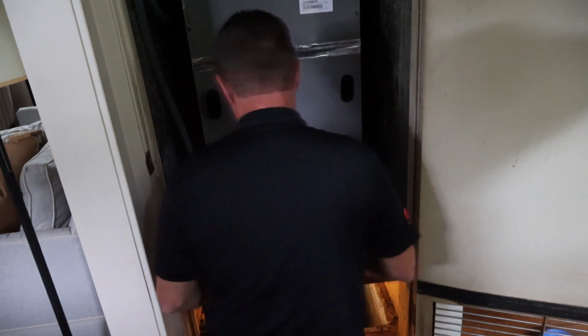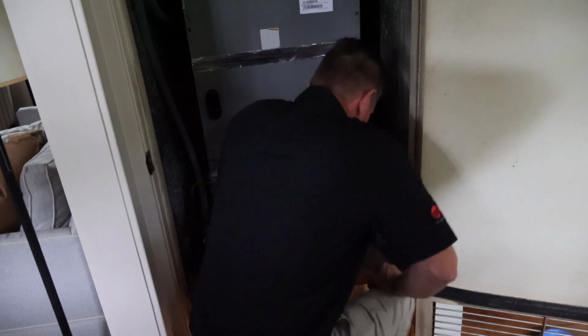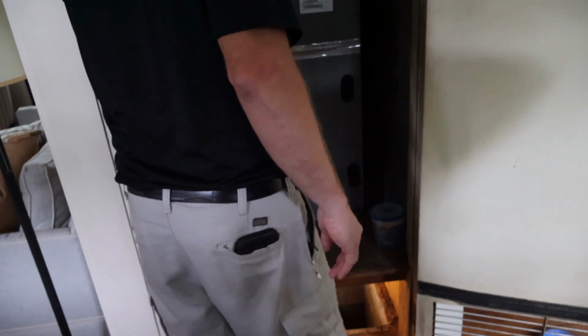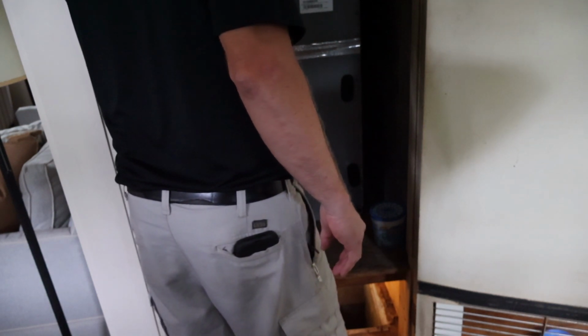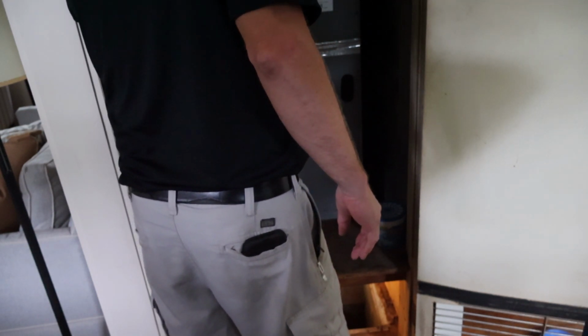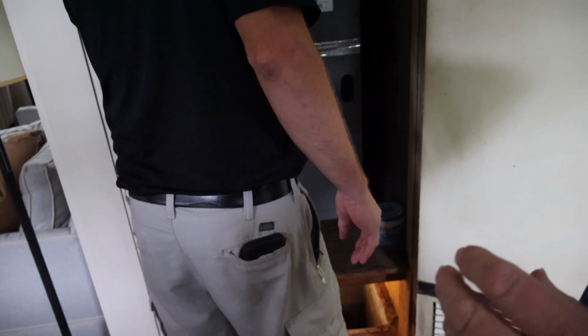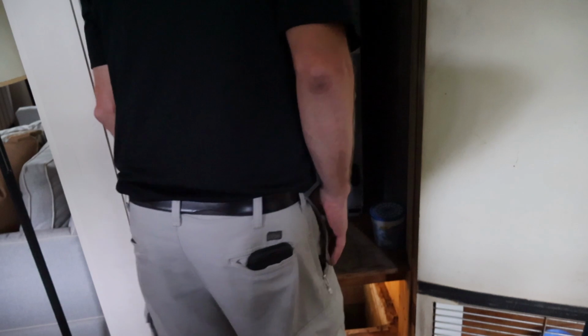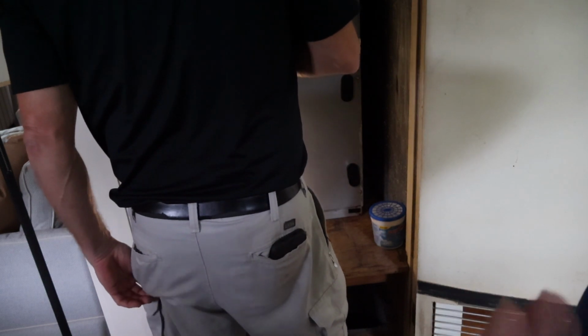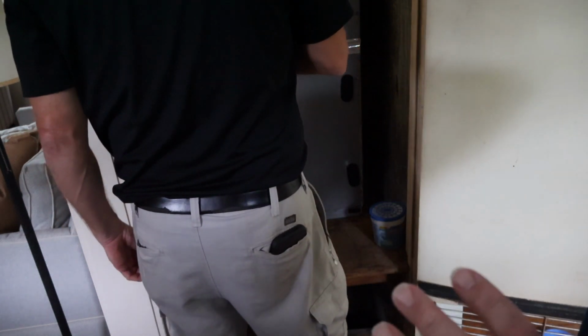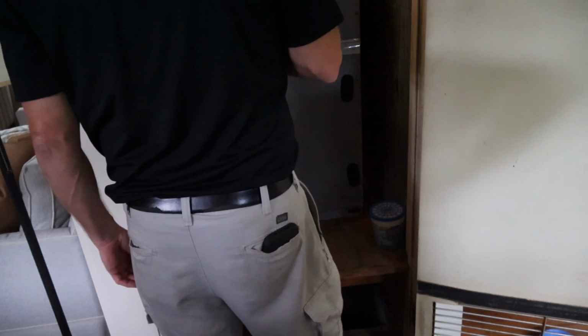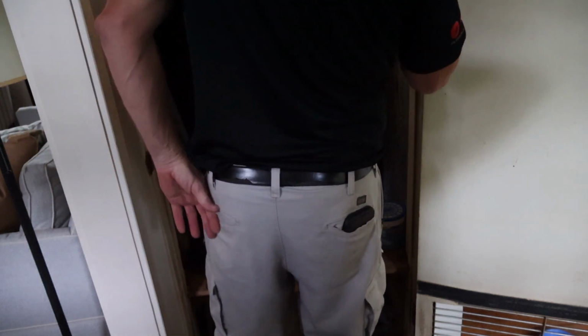And we'll come back in after we service the outdoor unit. One reason we do that is if the system is low on refrigerant, we'll have to leak check. So instead of servicing the air handling unit and taping it back up, sealing the air handler doors, we'll go outside, confirm the Freon's okay, and if it's not and we've got a leak somewhere, we'll have to take the panels back off to do a leak check. So that's why we like to do the condensers first.